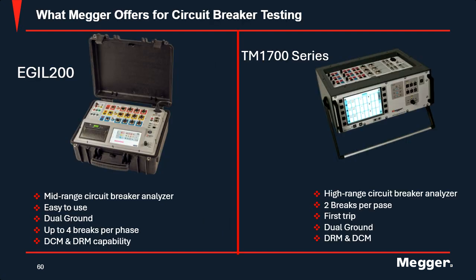Megger does offer a few products for circuit breaker analyzing test sets. Starting with our mid-range, we have an EGIL200. It's relatively easy to use. It doesn't require much interaction from the customer. You can obviously put in all your information for your specs, your timing tolerances, and your travel tolerances. However, if you just want to get everything hooked up and go, you can put all that in on the backside. It does allow for dual grounding. You can do up to 4 breaks per phase, and it is DCM and DRM capable.